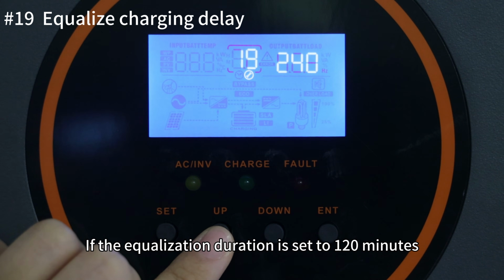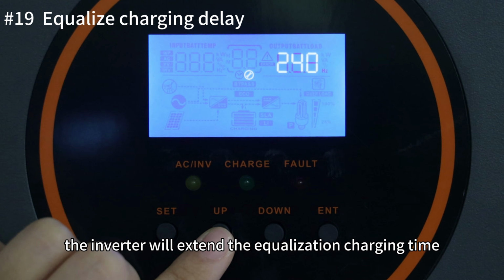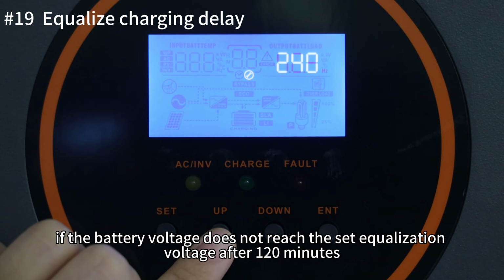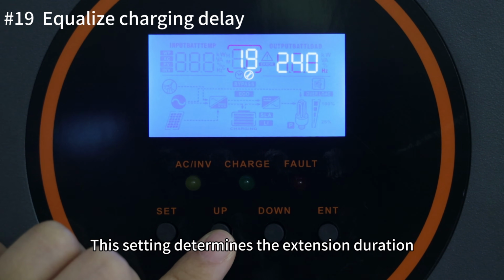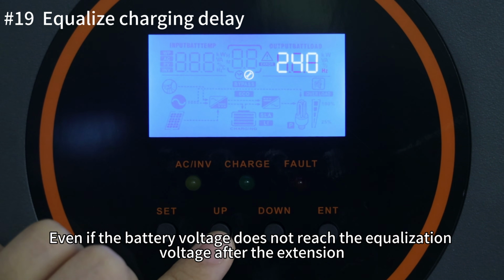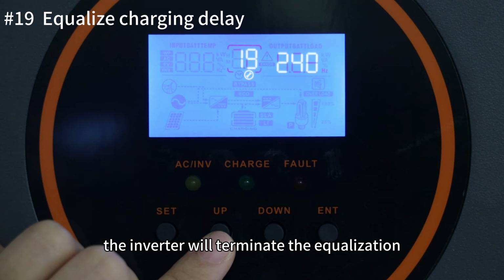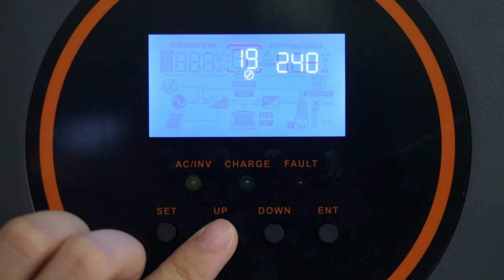If the equalization duration is set to 120 minutes, the inverter will extend the equalization charging time if the battery voltage does not reach the set equalization voltage after 120 minutes. This setting determines the extension duration. Even if the battery voltage does not reach the equalization voltage after the extension, the inverter will terminate equalization.